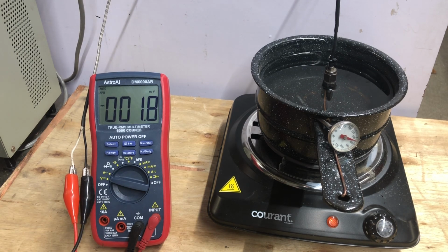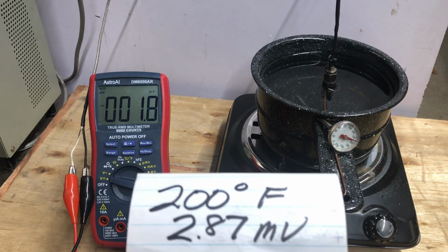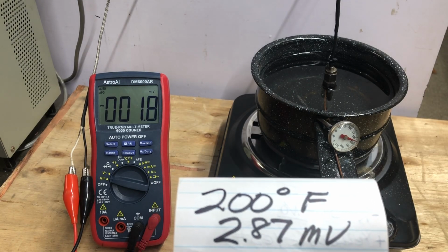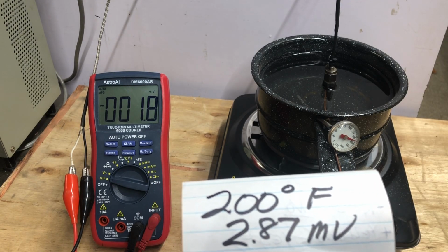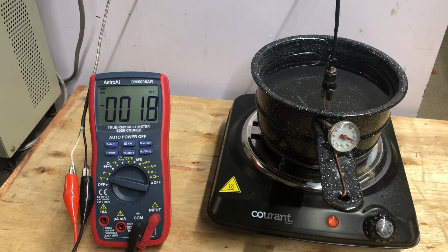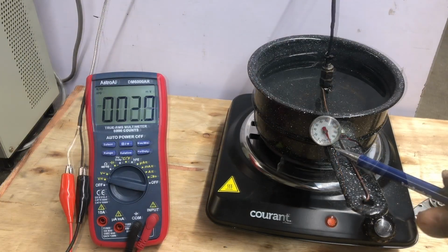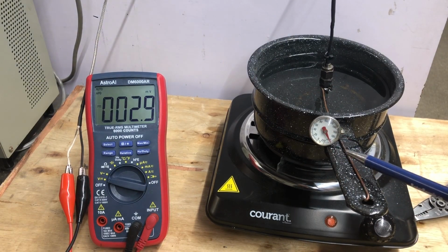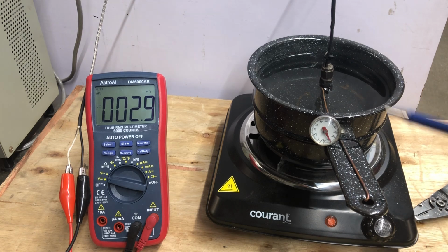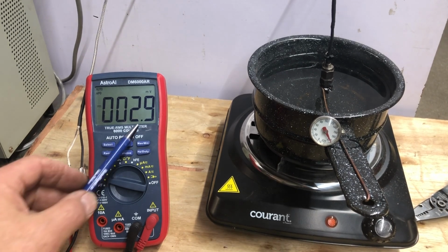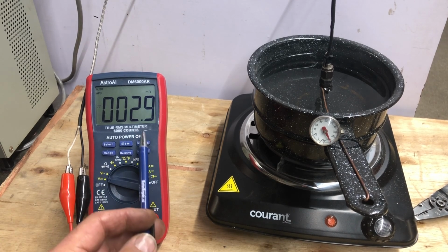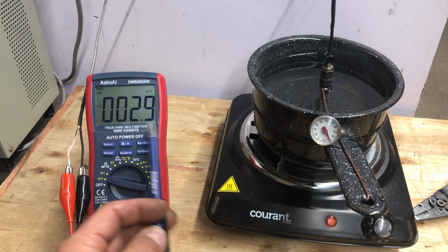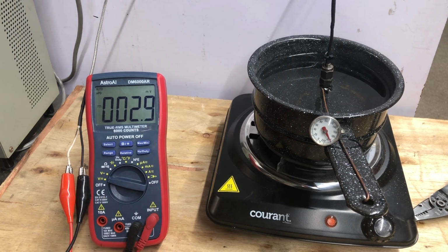It's going to come up, and what I'm looking for in the end is the spec from before, which is 200 Fahrenheit, 2.87 millivolts. Now, I'm either going to get 2.8 or 2.9 because there isn't anywhere here to get a 7. So we'll see what happens. So I'm at 200 degrees. I had to reposition the thermometer because it was a little bit too far down. That's why it's at a different place. At any rate, I'm at 2.9. So I can't get 2.87, but 2.9, I'll take that. So I would say that one is absolutely in calibration.